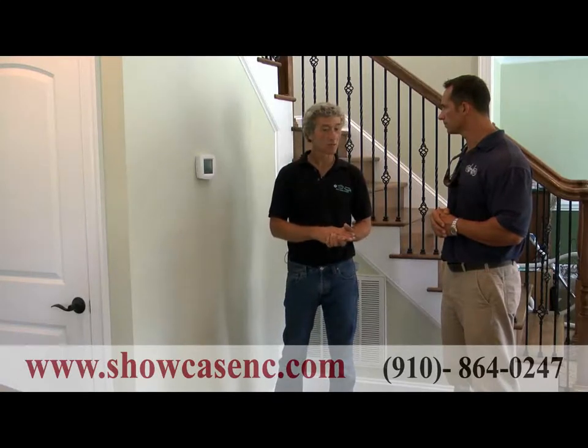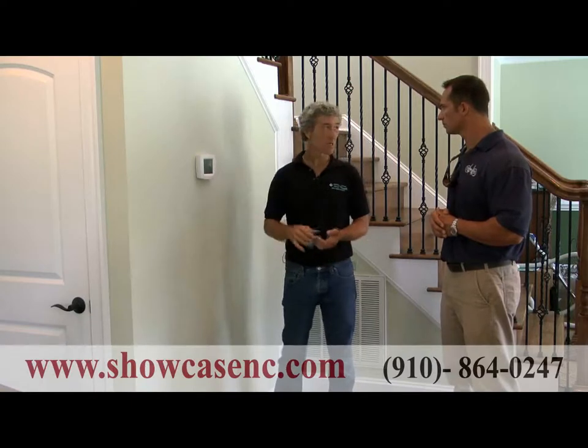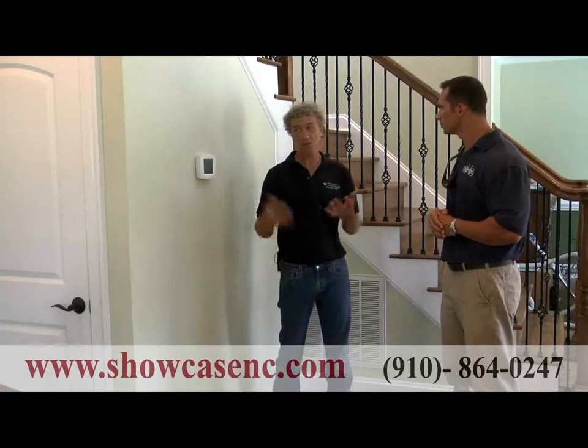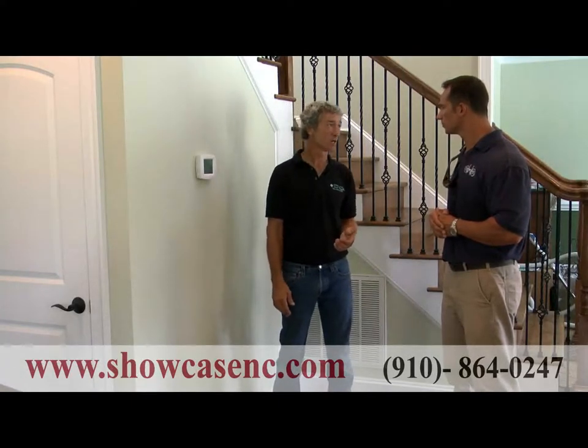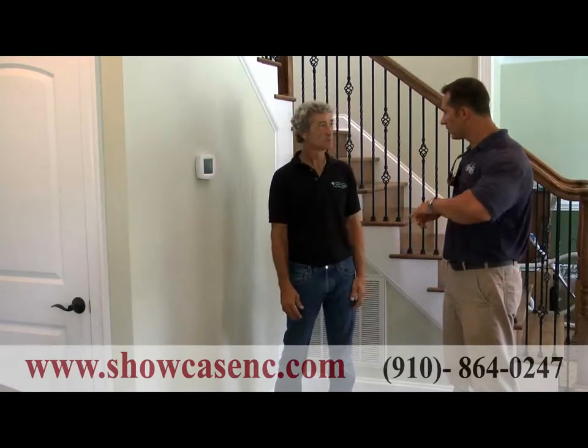Let's talk about that real quick. The variable speed air handlers, when you go from the on selection on your fan, it's not a traditional air handler that's going to go wide open. It only runs at 25%. So actually, the homeowner would never even probably hear the fan running, and you could get constant circulation in your home at a very, very low cost. But if it needs it, then it'll ramp up?